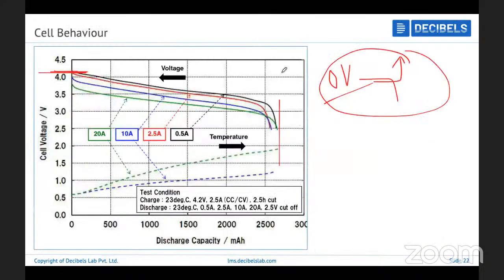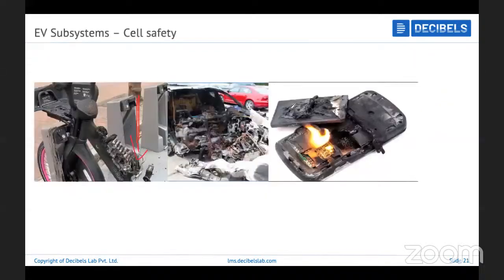The same way, all the cells have different over voltage limits, under voltage limits, over temperature limits, under temperature limits, and over current limits. Largely, these are very basic functions that a BMS should ensure, maintaining the battery or cells within the specific bandwidth. If you do not maintain it, you will create a problem for the battery's life, or a battery fire. So you need something that takes care of these scenarios.